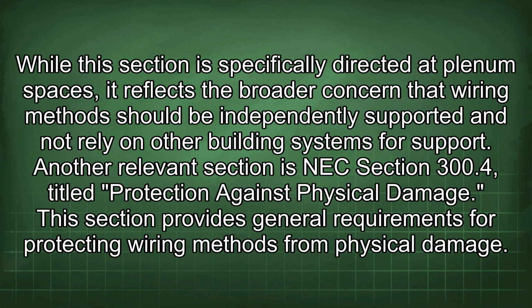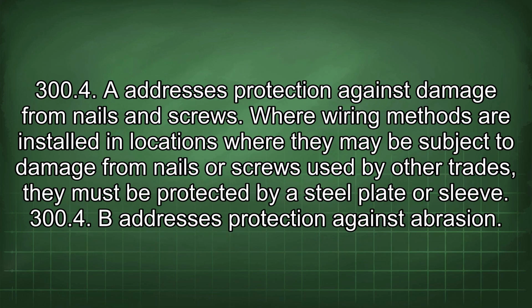While this section is specifically directed at plenum spaces, it reflects the broader concern that wiring methods should be independently supported and not rely on other building systems for support. Another relevant section is NEC Section 300.4, titled Protection Against Physical Damage. This section provides general requirements for protecting wiring methods from physical damage.